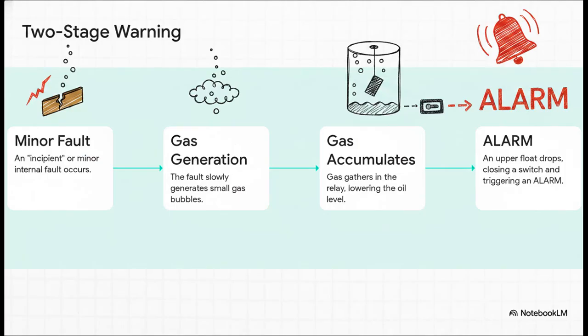Okay, so stage 1 is the alarm. This is for those minor, slow-developing faults. Imagine a tiny piece of insulation starts to break down. This slowly creates little gas bubbles, which float up and get trapped inside the Buchholz relay. As more gas collects, it pushes the oil level down inside the relay, and an upper float drops with it. That drop closes a switch, and an alarm goes off. It tells the operators, hey, something's starting to go wrong in here long before it becomes a disaster.